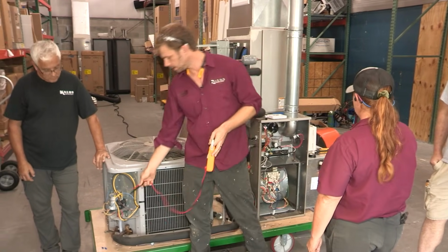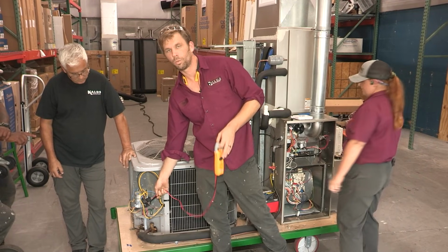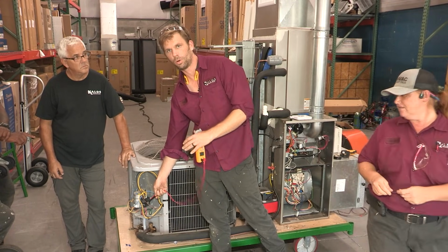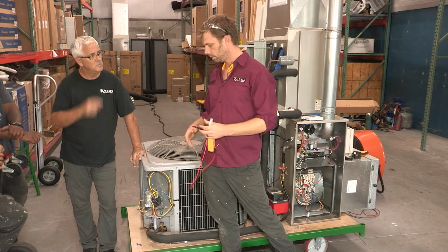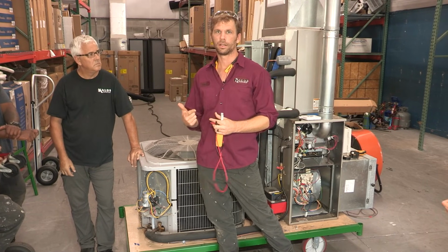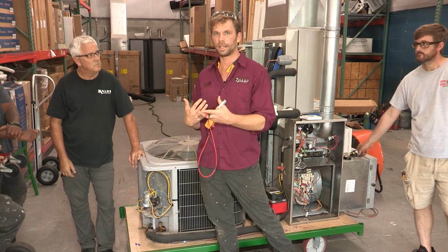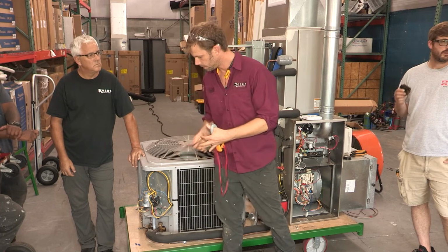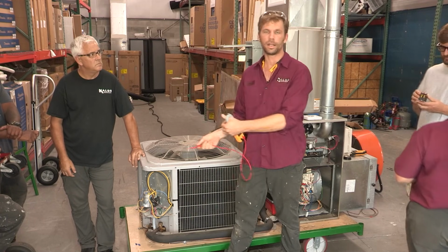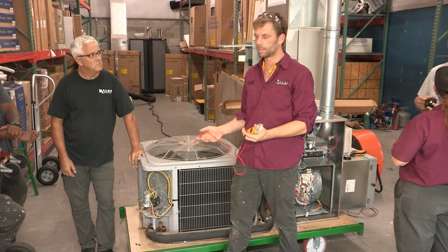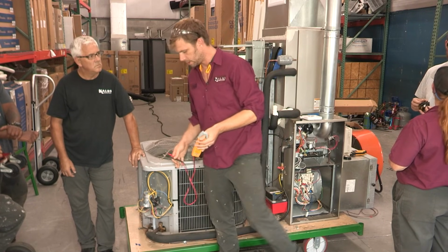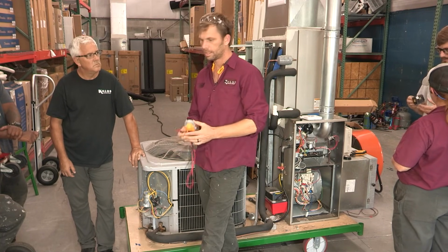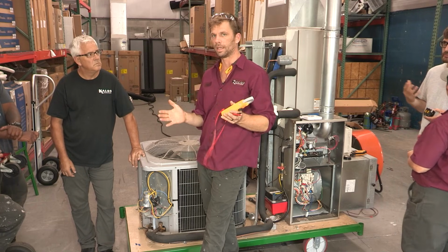The load that this produces is actually generated once the voltage has been applied to the coil. It's a load that's generated by the magnetic field, so you have a magnet that pulls in and that generates resistance. But if we don't have electricity on it, then we can't measure its true resistance. At this point, we're just basically doing a test to see if we're anywhere close to where we might be.